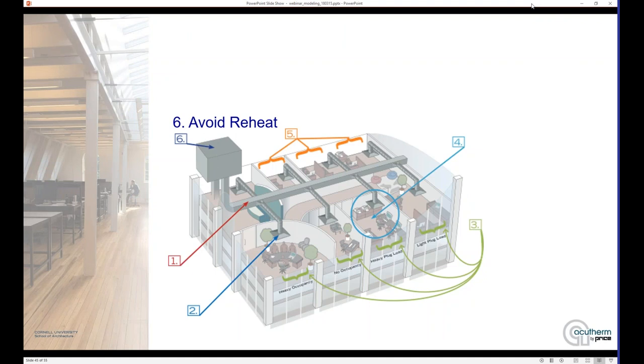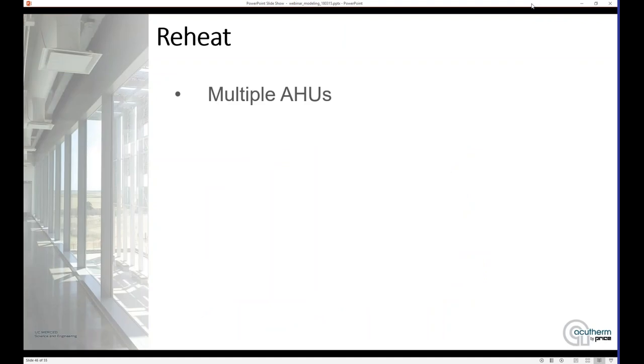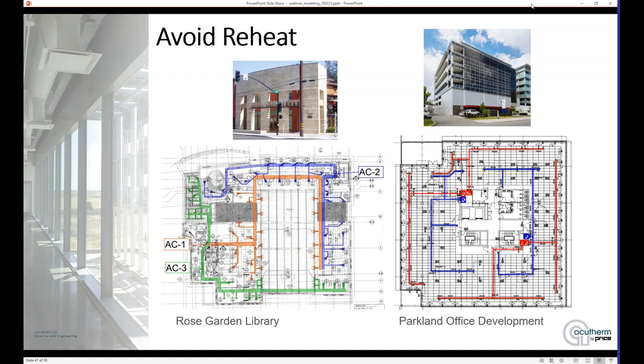Lastly, we're going to talk about reheat. Reheat, by definition, is a waste of energy because we're taking energy that we've already cooled and now we're heating it back up again. So if there's any way to avoid or minimize its use, we want to try it. One good way is in your designs — if you can work with a multiple air handling unit system to create your zoning, then you won't need any reheat. For example, here's a little library on the left with three different air handlers — in this case rooftop units — separating the perimeters of the building from the interior and avoiding reheat.